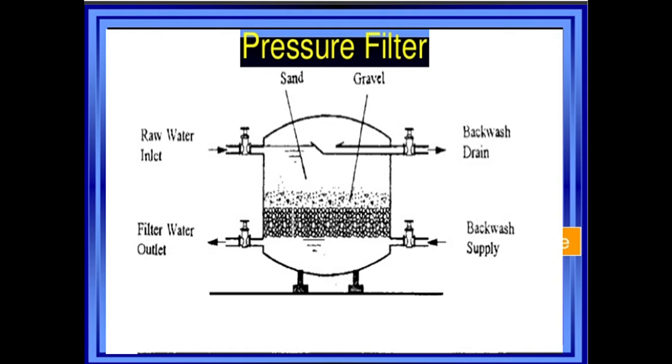The diagram shows the gravel and sand bed, backwash drain, backwash supply, and filtered water outlet. Pressure filters are of the same construction as gravity type rapid sand filters, but the filter bed together with the filter bottom is enclosed in a watertight steel pressure vessel. The driving force for the filtration process is the water pressure applied on the filter bed.